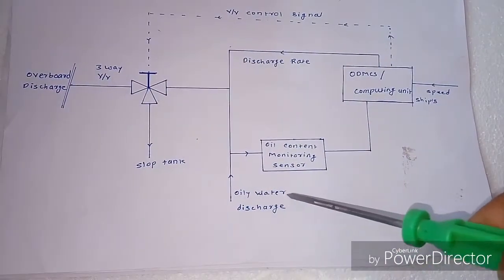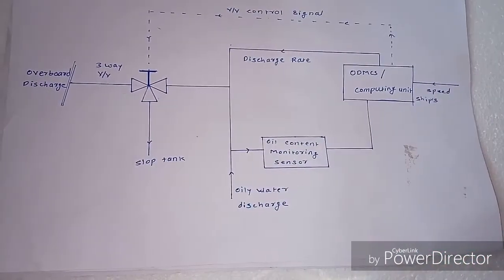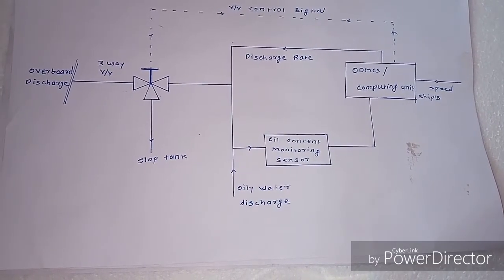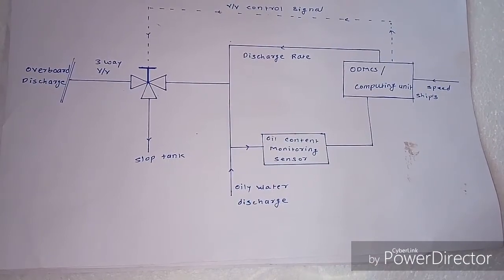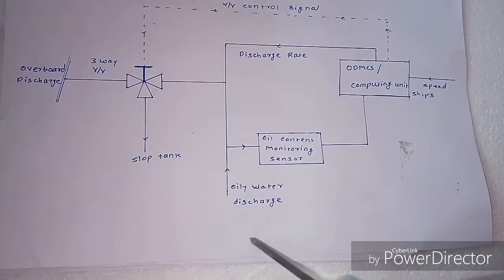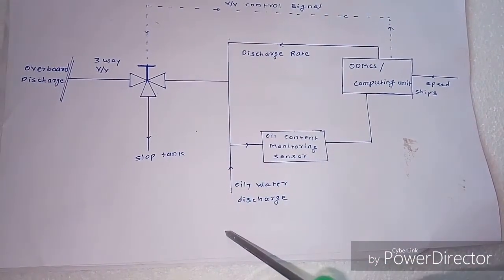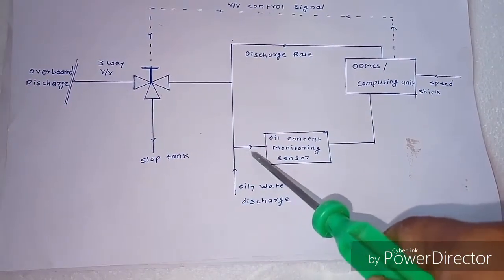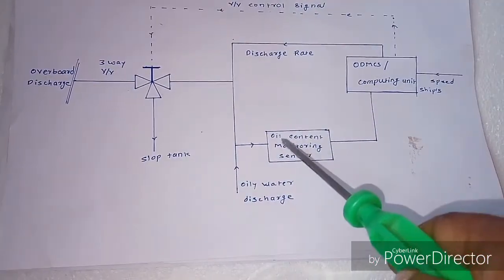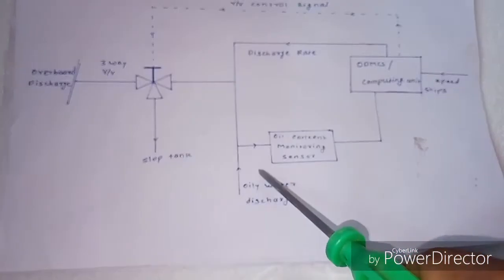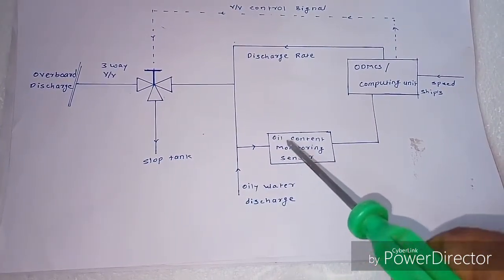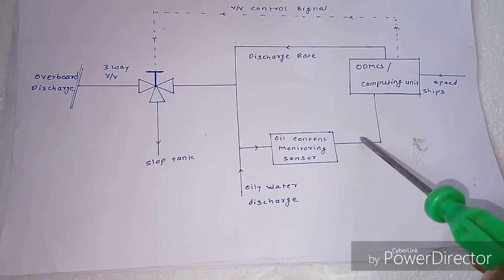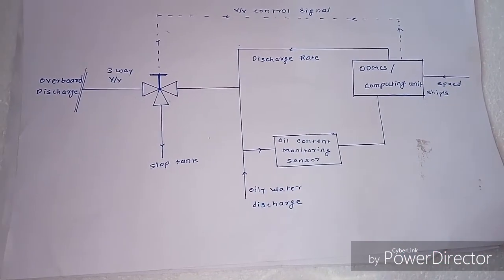We already know the Oil Content Monitoring Sensor — if you don't know, please watch my previous video where it is completely discussed. Here there is a slop tank where cargo residue is collected. It is to be discharged through this pipeline, and this pipeline is monitored by the sensor, which monitors the oil content. The oil content should not be more than 50 ppm. This measured value is transferred as a signal to the computing unit.